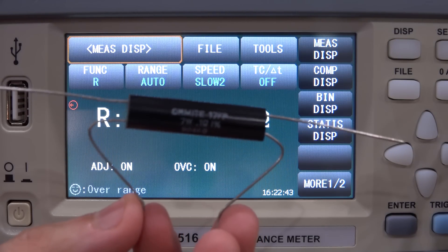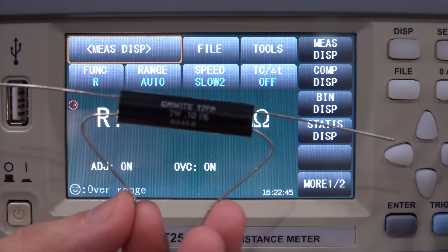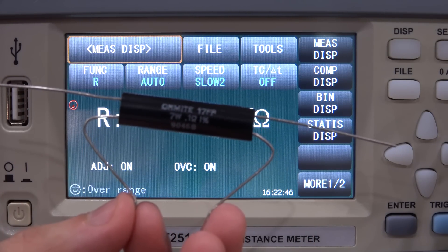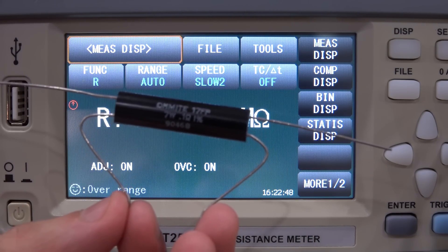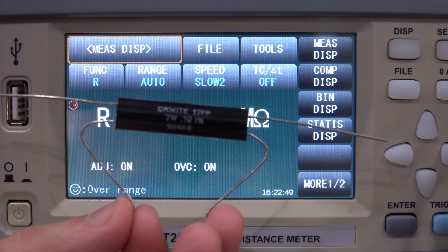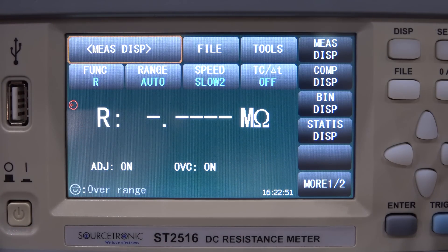Now one thing to keep in mind is that these resistors do have sense ports as well as the actual ports of the resistor. We should be using them in that four wire measurement mode but in reality our Kelvin clips make connections at the interfaces so it's not ideal but it's good enough.